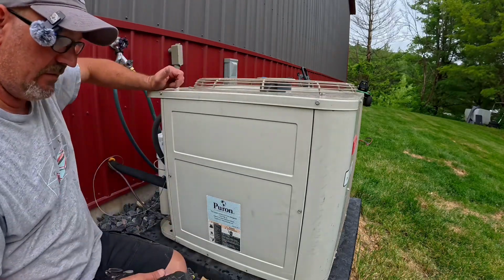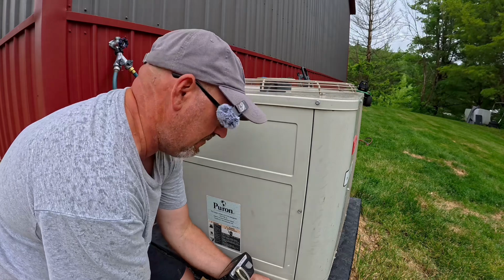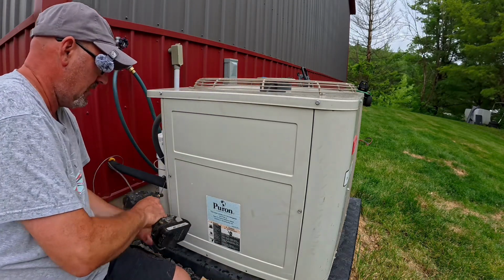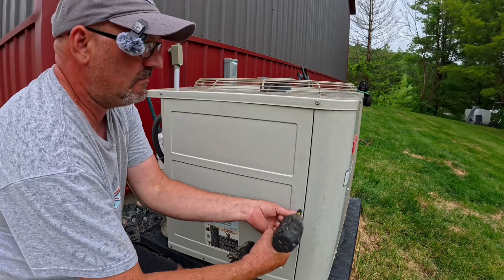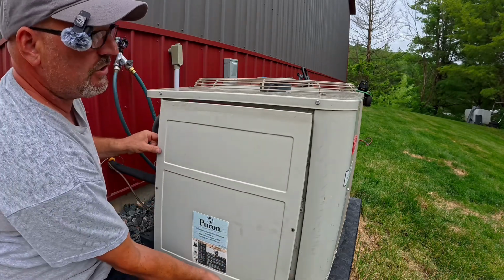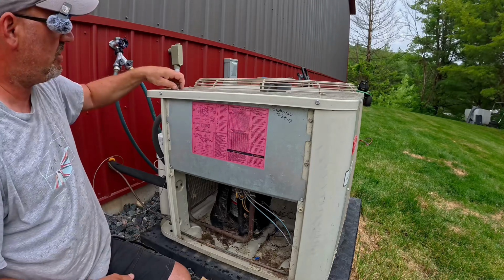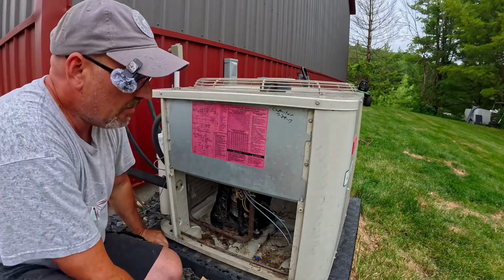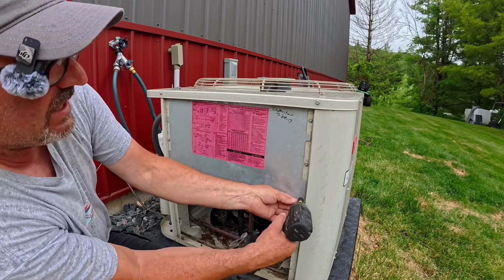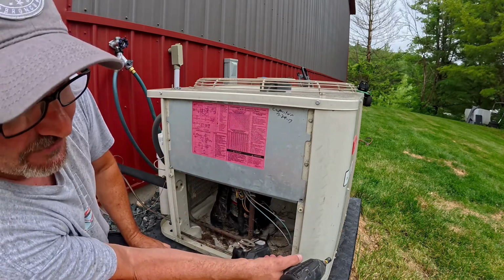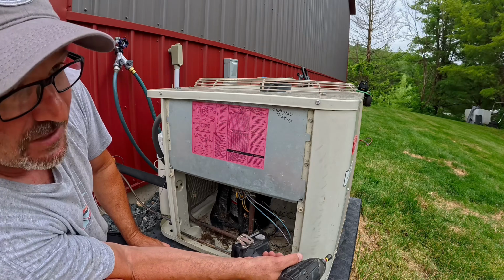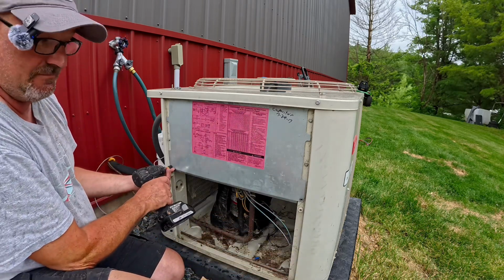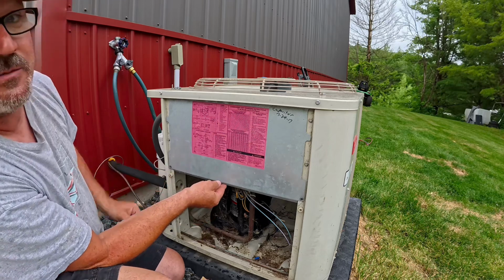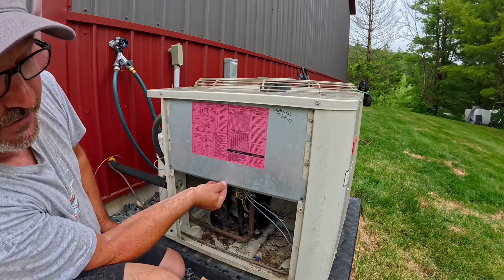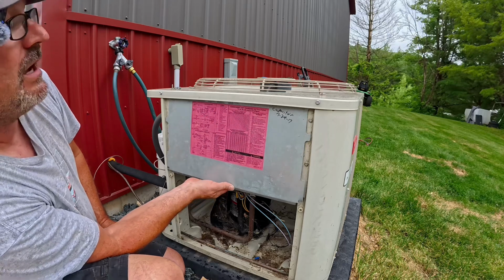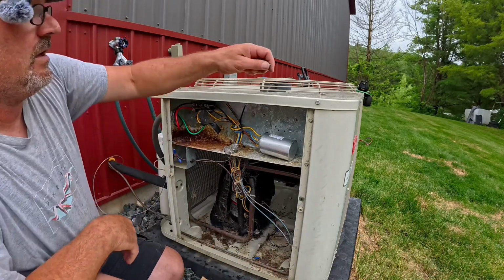So again, scenario, the indoor unit's running, the outdoor unit is not. So now we're going to go into our service panel. We've already verified that we do have 220 volts coming into the disconnect box. The disconnect box is now back together. Behind this panel, again, every air conditioner is different, but at the end of the day it's pretty much the same concept. Just got to figure out which way yours is set up. So we're going to carefully, because we got high voltage in here, and again, if you're not comfortable playing with high voltage, call a technician, stop right here. I'm not concerned with it.